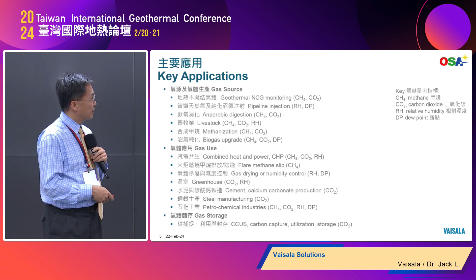The light source, the infrared light source, does not have to be changed for 10 years. It's the only probe on the market that can have such a long lifetime and stability on the light source, which is probably one of the most critical parts of any IR device.